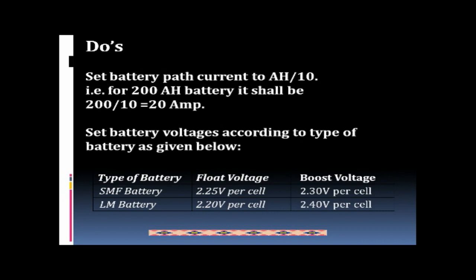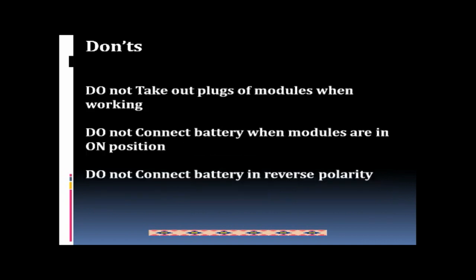Don'ts: Do not take out plugs of modules when working. Do not connect battery when modules are in on position. Do not connect battery in reverse polarity.